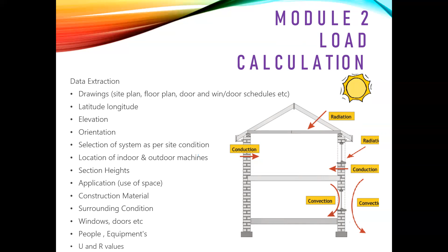And after that, we will select a system, for example split AC, window AC, or ductable split, as per the site condition. And we will analyze various outdoor and indoor conditions, section heights. As you know, we have beam bottom height, we have ceiling clearance. For ducting purposes, we need that also. And whether you are using it for an office, school, or residential space will also affect the load calculation. So that will be explained. And construction materials, surrounding conditions, windows, doors, etc., people, equipment, all these components actually have a great impact on load calculation. Okay, and U and R values, that is nothing but the overall coefficient of heat transmittance and resistance. Maybe you are already aware of this one. We will have a discussion about this also in great detail.